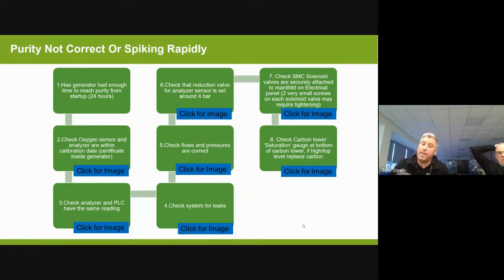We're going to check the system for leaks, and check flows and pressures using our test sheet. You need to ensure you have the right tools for that as well, so that would be some sort of flow meter that can measure up to 500 litres, or whatever the output is. We're going to check the solenoid valves are securely attached, and we're going to check the carbon tower saturation gauge at the bottom to ensure it's not saturated. That will give us a good basis to ensure the system works correctly and that the oxygen content is maintained at the level that is required.